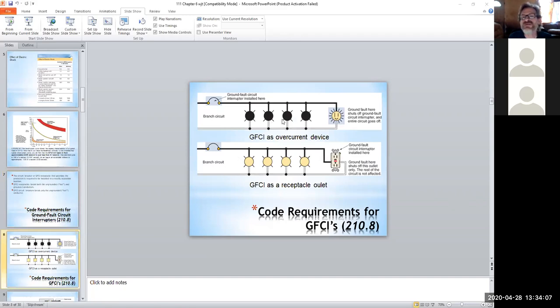Laid out just like this - how many can it protect? If anything were to happen on anything within that branch circuit, the GFI is protecting it. And of course, back here you still have your circuit breaker in the panel doing its normal job. But the GFI is out there protecting all of those devices, making sure that if anything happens to any one of them, it will trip.